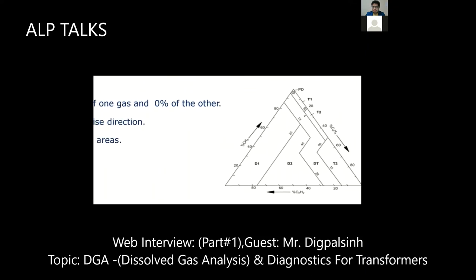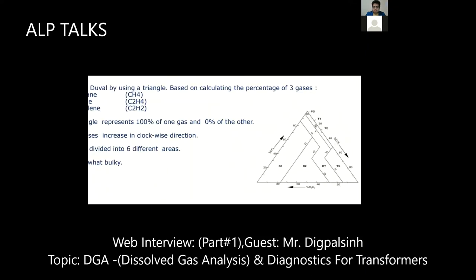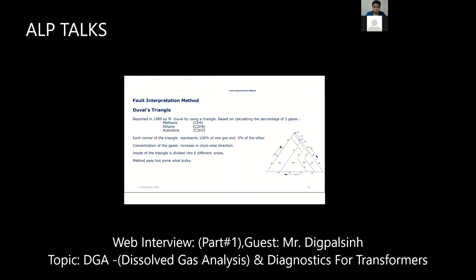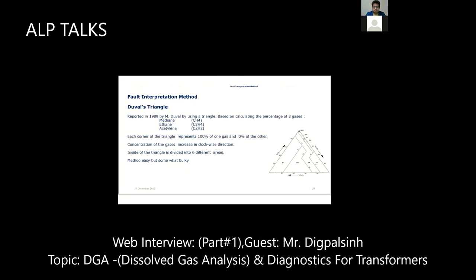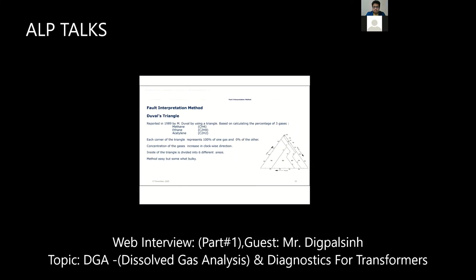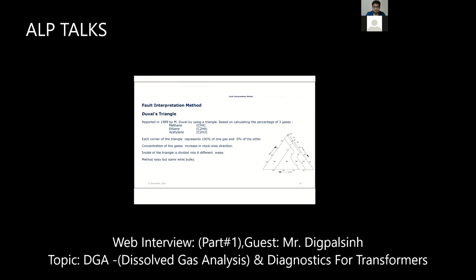Actually, Duval has invented more than 10 different triangles: for transformer oil, for the OLTC compartment, and for when it is not mineral oil but a natural ester or synthetic ester. He has invented a different kind of triangle for each. I have not memorized the exact number, but it is more than 10. And Duval is alive, so he is doing more research on the triangle.